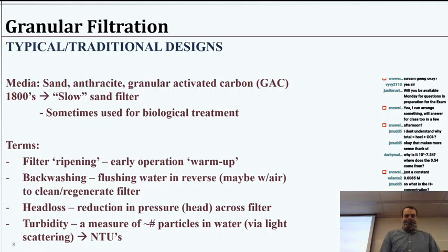Okay, so just a quick little bit of history and some info about our typical designs. I mentioned, but we're pretty much always using sand or some equivalent granular stuff. Anthracite is popular. Granular activated carbon is another one. A lot of times they'll have a mixture of a couple of them, right? They'll have half of it sand, or maybe 40% sand and 60% anthracite, something like that, just based on their practice, what they find works best for their situation.